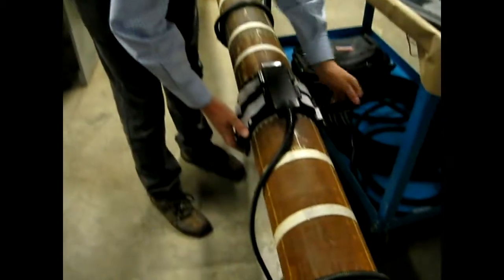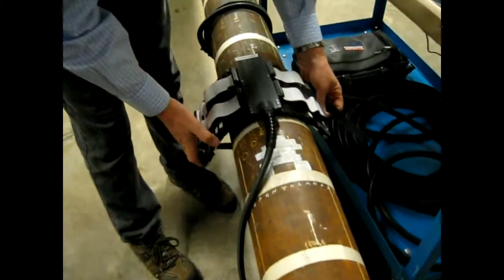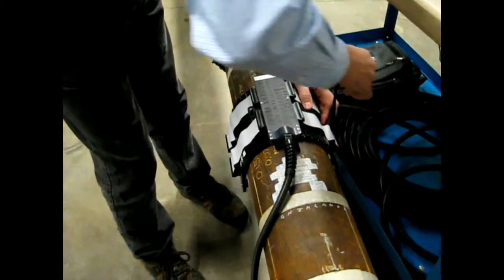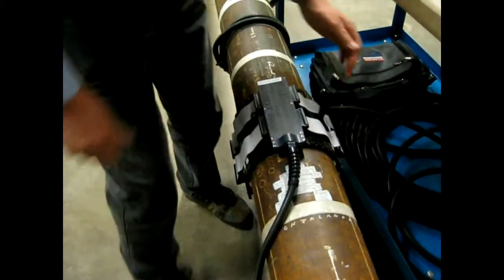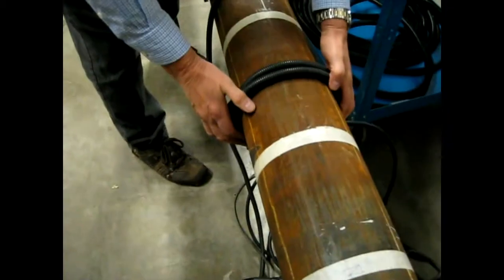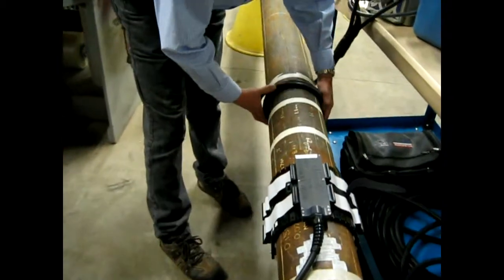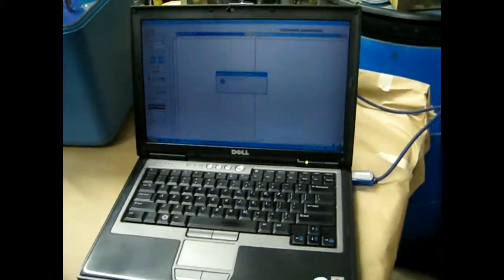So what does the rest of this pipe look like? What we have to do now is reposition the blanket probe either to the side of that spot or just move it down the pipe. In this case I'm going to move it down the pipe. We've got this all marked out in blanket probe size increments. I need to readjust my exciter coils, which are providing the field, then type in a new file name and hit go.